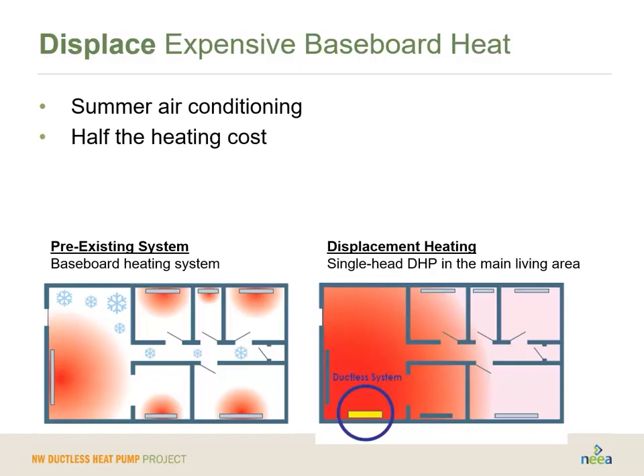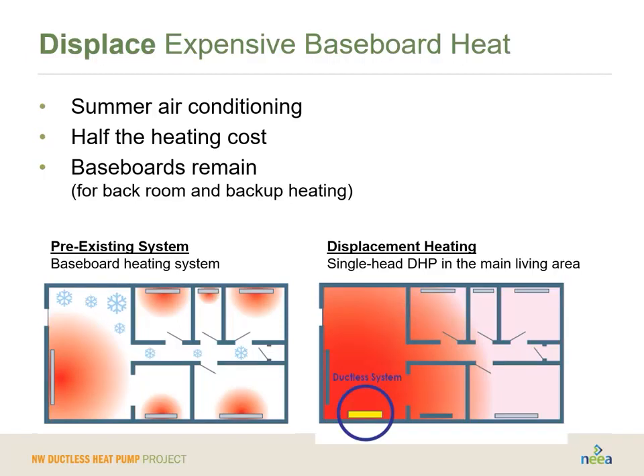It cuts the heating costs in half for the building, but you can still keep those baseboards. In the main body, they can be used for the really, really coldest day of the year where you just need that little extra oomph, and it allows you to still keep heat going in the bedrooms, but maybe you set the bedrooms down a degree or two. So maybe if you have the main body heated to 69 or 70, maybe you keep the bedrooms at 67 or 68. And these two systems are not competing with each other very often. It only really will kick on that baseboard heat when the overall building drops down cool enough. And most homeowners find this to be a very acceptable way to heat and cool their home.